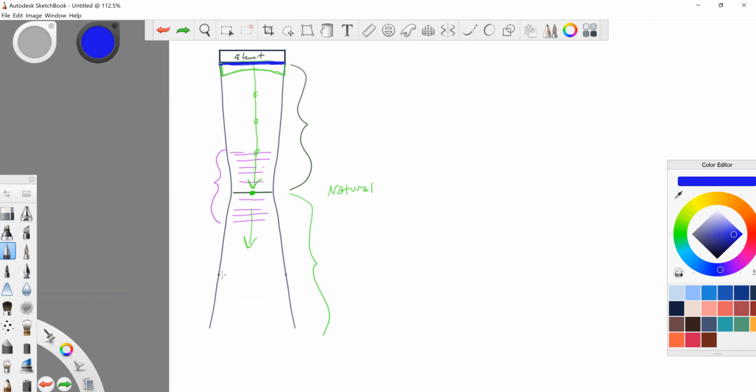I keep drawing my beam a little bit off, but you get the idea. So everything after the aperture is immediately getting smaller. And then after the focus, it starts to widen out, but it's not until 2 near zone lengths that it's equal to the aperture.